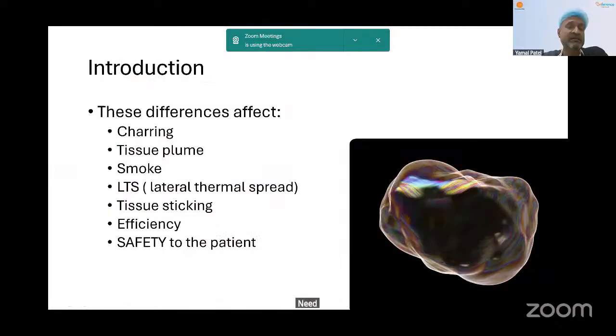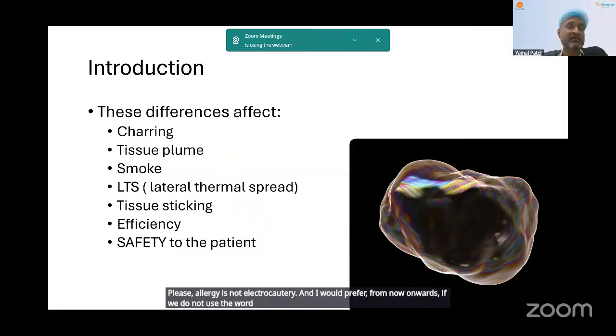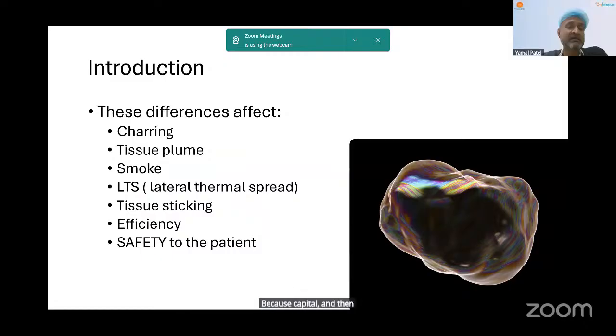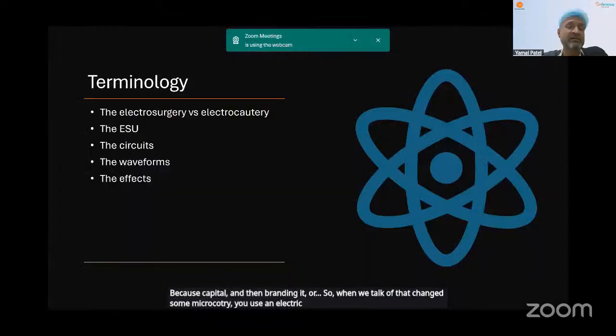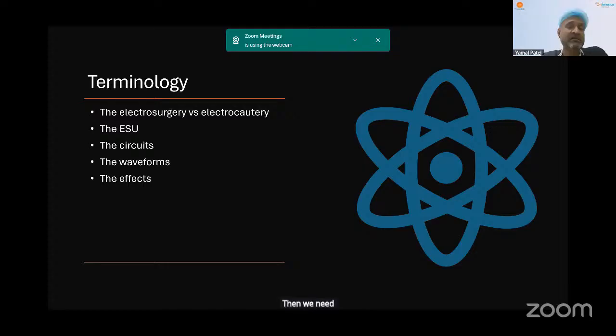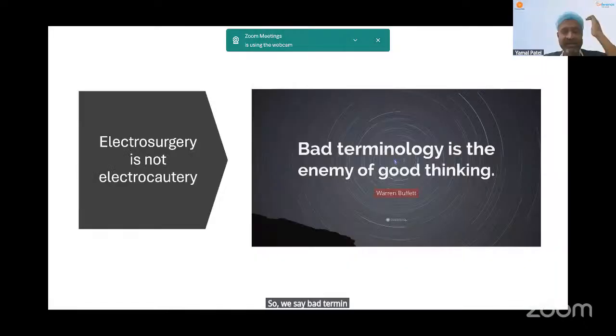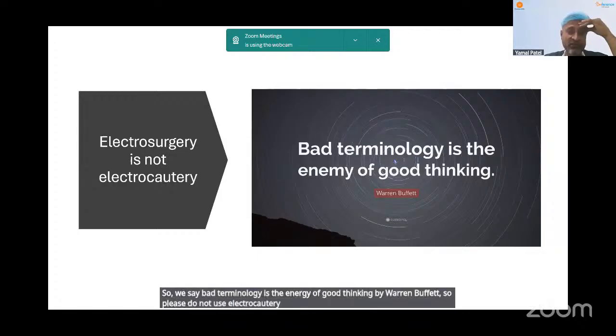I want to be very clear about the terminology to be used. Please, electrosurgery is not electrocautery, and I would prefer that from now onwards we do not use the word cautery. With electrocautery, you use electric energy to heat a metal element and then touch it to the tissue, which is not what we do. We use electrosurgery or diathermy. Then we need to know about the ESU, the electrosurgical unit, the circuits, the waveforms, and the effects. Bad terminology is the enemy of good thinking, as Warren Buffett said. So please do not use electrocautery. It is not the same as electrosurgery.